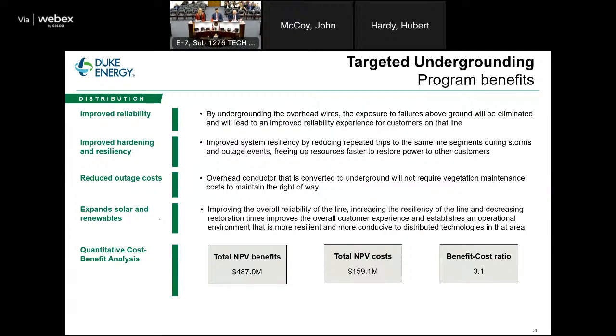The benefits of targeted undergrounding: it eliminates the risk of outages due to overhead causes. The accessibility we have by being front lot reduces outage durations, and upgrading historically outage-prone assets lessens the quantity and duration of outages during extreme weather across the system, which helps bend the restoration cost curve down. It also eliminates vegetation management costs for all the line segments converted with this work - that's vegetation line miles no longer needing to be trimmed, a savings for all customers. Lastly, a reliable, resilient grid supports growth in DERs and EV adoption, and the benefit cost ratio for this work is 3.1.